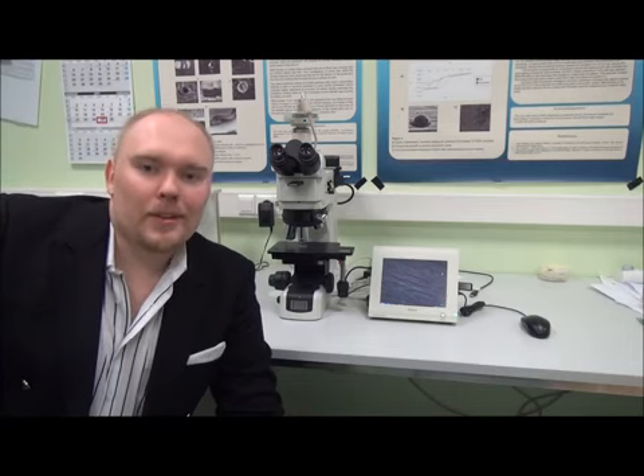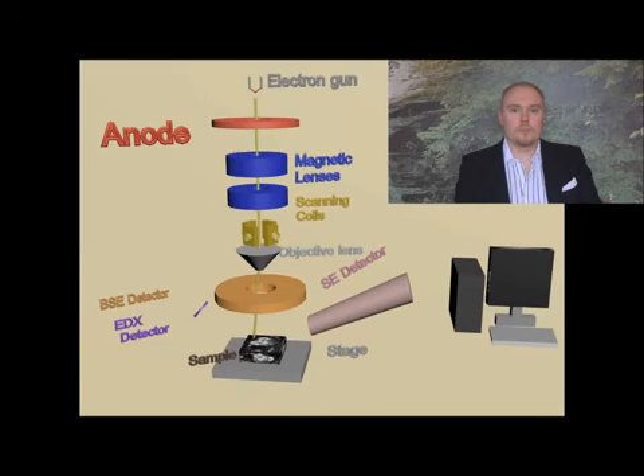So let's take a look at the most important components of the scanning electron microscope. On the image you can see the electron gun, which emits electrons. The anode, the lenses and the scanning coil are there to manipulate these electrons. And also you can see on the image 3 detectors, which basically catch all the signals which are emitted by the sample as electrons interact with it.